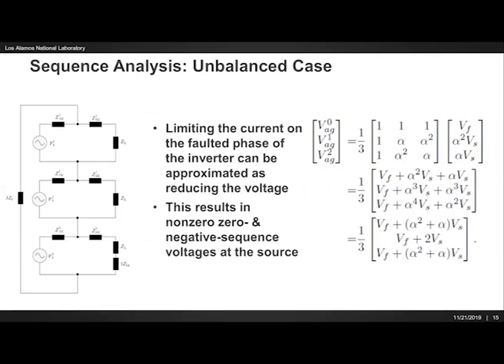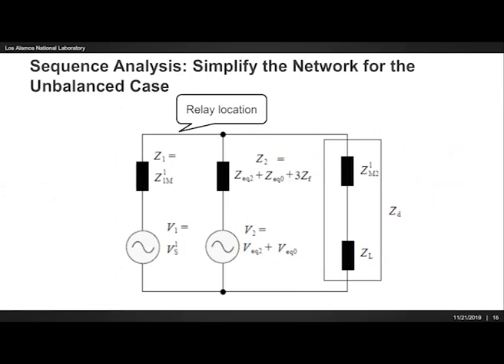Now, what we saw in the previous interconnection of sequence networks was there's only a positive sequence voltage. Now, for the case of an inverter which is operating in current limiting mode, as I described, I now have the presence of negative and zero sequence voltages on my equivalent sequence networks. So the voltages and currents that I'm going to be measuring are now going to be somewhat different. And this gives me a new simplified network where I get a second source, which is equal to the sum of the zero and negative sequence voltages produced by the inverter.